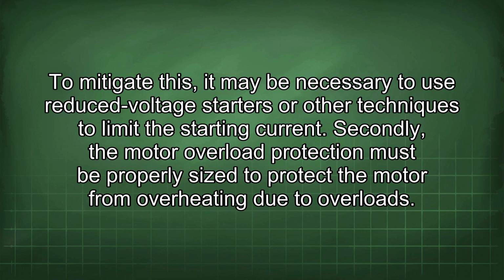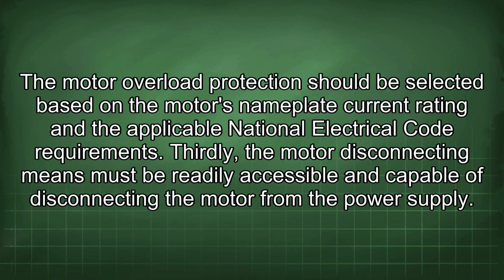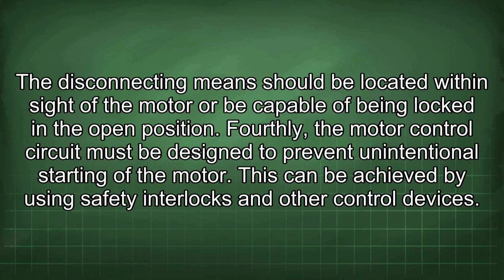Secondly, the motor overload protection must be properly sized to protect the motor from overheating due to overloads. The motor overload protection should be selected based on the motor's nameplate current rating and the applicable National Electrical Code requirements. Thirdly, the motor disconnecting means must be readily accessible and capable of disconnecting the motor from the power supply. The disconnecting means should be located within sight of the motor or be capable of being locked in the open position. Fourthly, the motor control circuit must be designed to prevent unintentional starting of the motor.